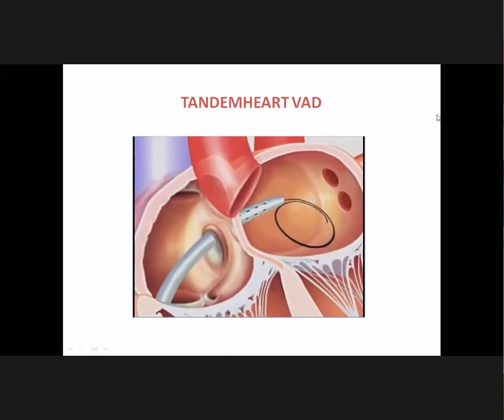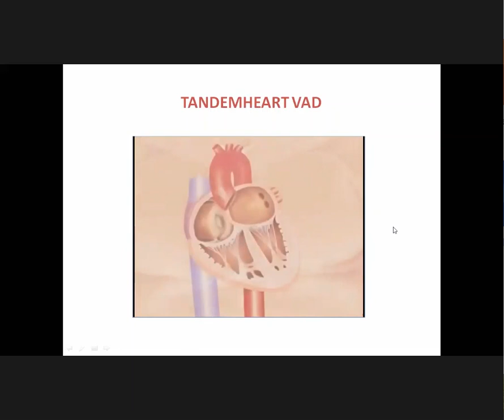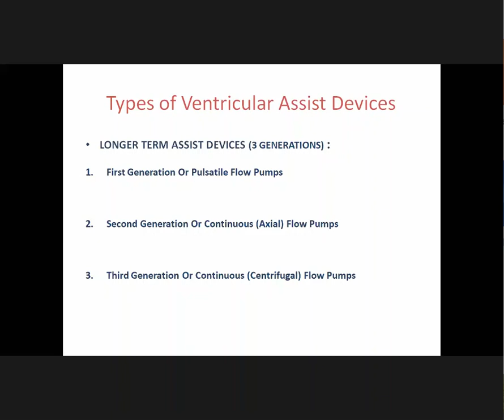The tandem heart can be rapidly inserted in the cath lab or operating room in as little as 30 minutes. Use a standard transeptal puncture. Next one are the long-term assist devices. Long-term assist devices can be classified into first generation or pulsatile flow pumps, the commonly used second generation continuous flow pumps, and the most recent ones which are coming into more common use, that is the third generation continuous flow pumps.